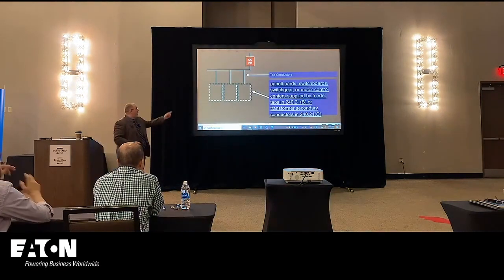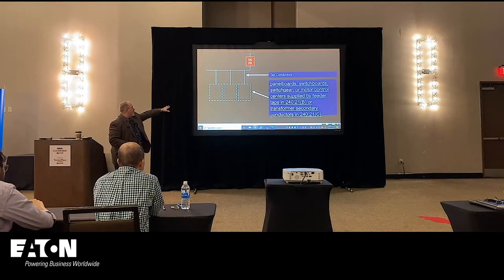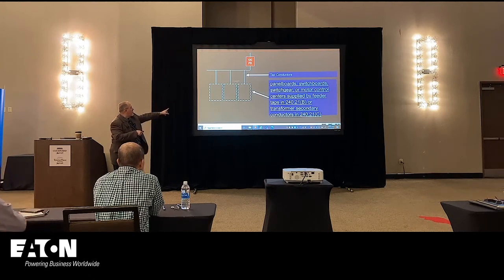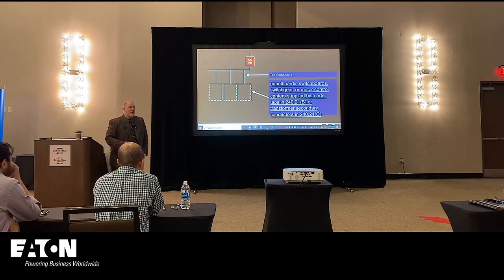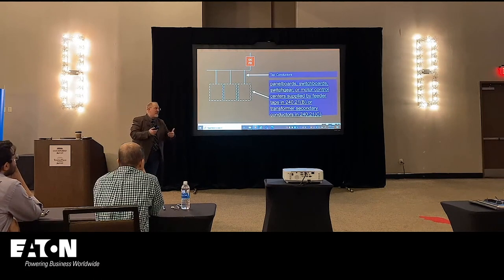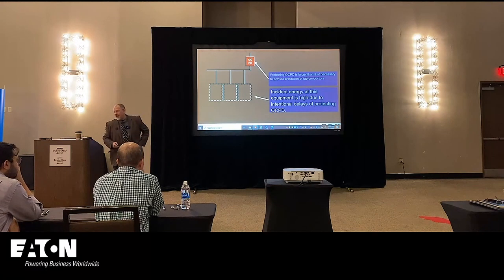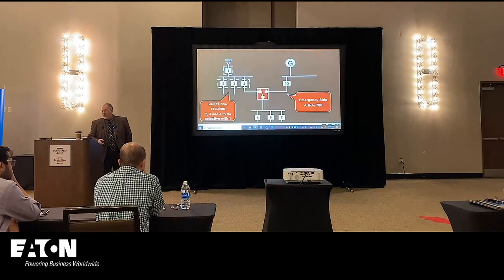So anyway, there's your OCPD, there's your tap conductors, panel boards. That OCPD is sized larger than these tap conductor sizes. So you've inflated the size of the overcurrent device. I've increased the risk because the severity of any working on any of this down here is high. And this is my last one.